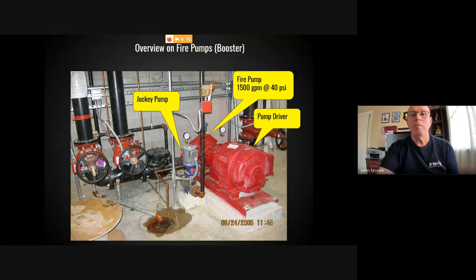There's also a jockey pump. Now the jockey pump is going to maintain pressure on the system so the fire pump doesn't constantly kick on. Think of it this way: any drop in pressure that would be less than the drop in pressure caused by an open sprinkler head, the jockey pump is just going to maintain pressure. If there's a drop in pressure from an open sprinkler head that activates for a fire, the flow is going to be great enough that it's going to override the settings on the jockey pump and the fire pump is going to come on.